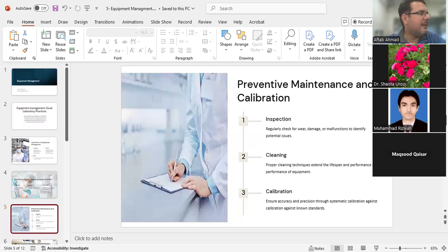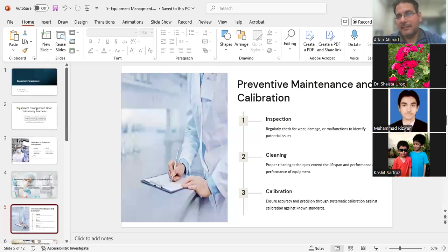Similar is the case with the weighing balance. I have a weighing balance. I think I took it into another laboratory, so I was not cleaning that, and what happened? The dirt got stuck beneath the surface area where we put the samples for the weight purpose. Even while I was checking, I was putting 2 grams and it showed this much on top, but when I put more sample, it was equal to 2 grams. So I checked it with another weighing balance, and then I found that it was giving faulty results.